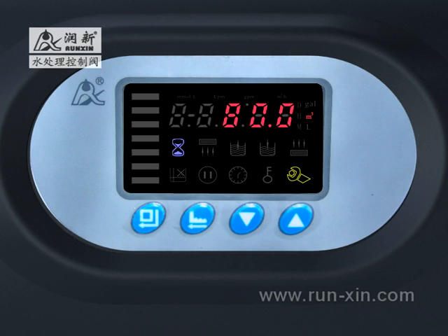Flow capacity 80 cubic meter is flashing. Press the up button until it changes to 555.5 cubic meter. Press the menu button. 555.5 cubic meters stops flashing. The program goes from setting state to inquiry state. At the same time, the setting symbol stops flashing. Flow capacity has been changed to 555.5 cubic meter. Press the return button to exit the menu. The screen shows the current working state.